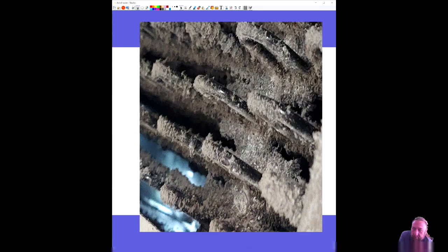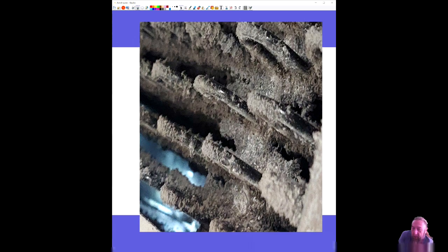But I never thought to look at the evaporator. Again, I did at that time, and we're talking about like 1990 something. I didn't do a lot of AC, so I didn't physically check the coils and see what's happening on the coils. But when you see ice like this, if nobody did any work on it, and it's iced up, your evaporator's probably iced up, and that would not be caused from a bad fan motor.